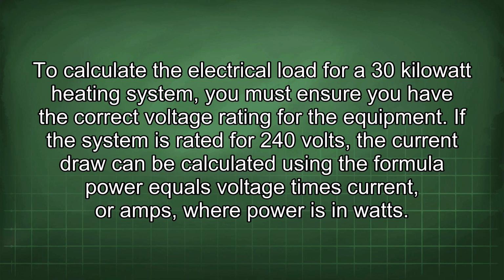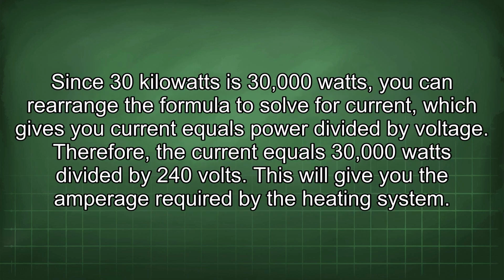To calculate the electrical load for a 30 kilowatt heating system, you must ensure you have the correct voltage rating for the equipment. If the system is rated for 240 volts, the current draw can be calculated using the formula power equals voltage times current, or amps, where power is in watts. Since 30 kilowatts is 30,000 watts, you can rearrange the formula to solve for current, which gives you current equals power divided by voltage. Therefore, the current equals 30,000 watts divided by 240 volts. This will give you the amperage required by the heating system.